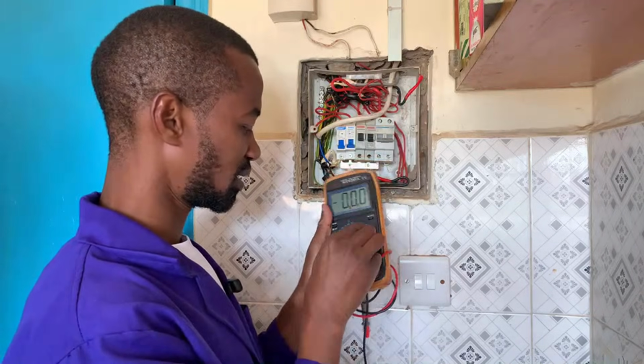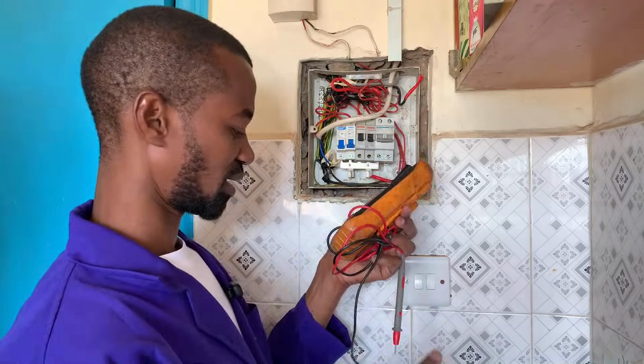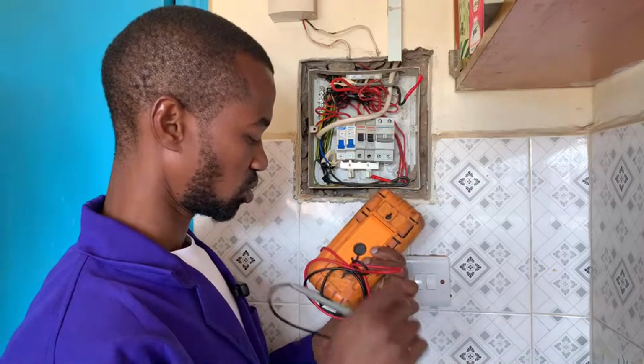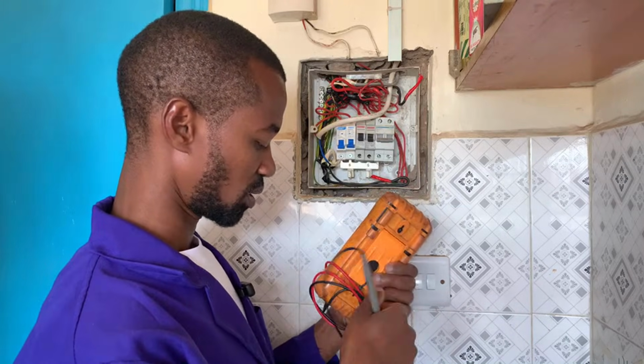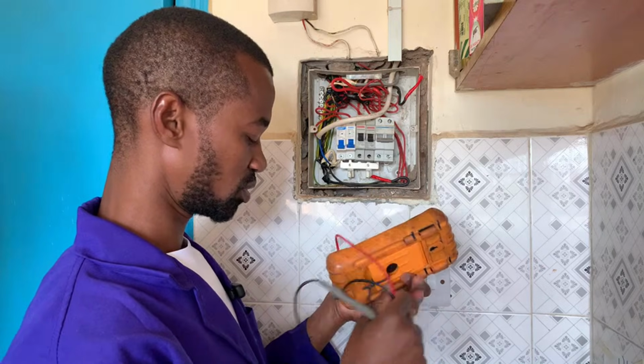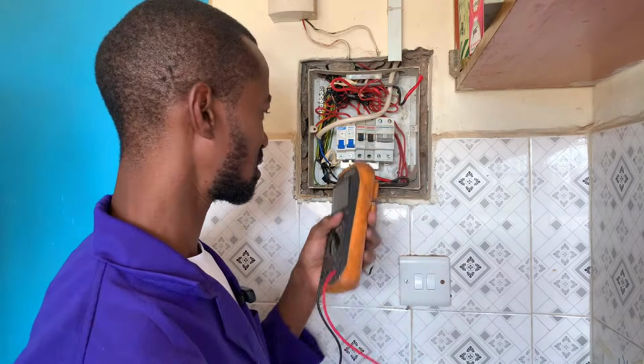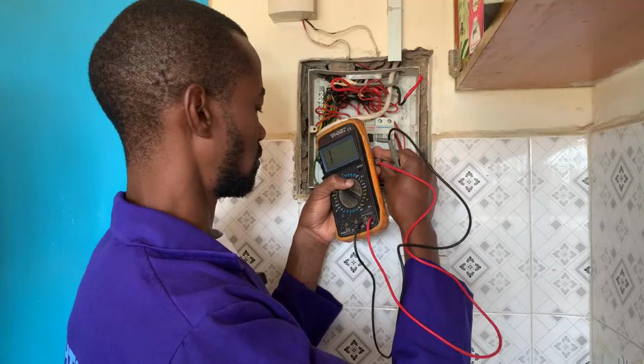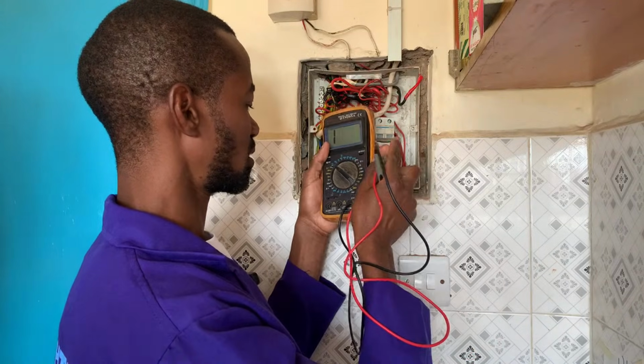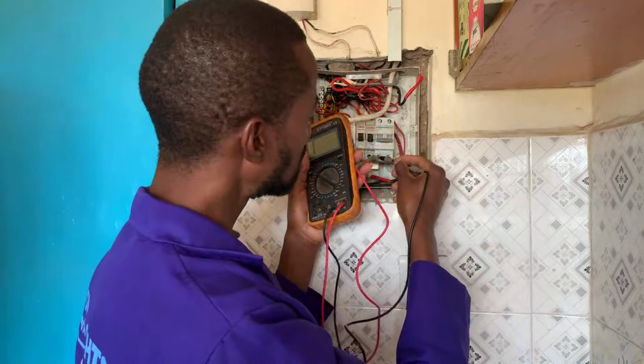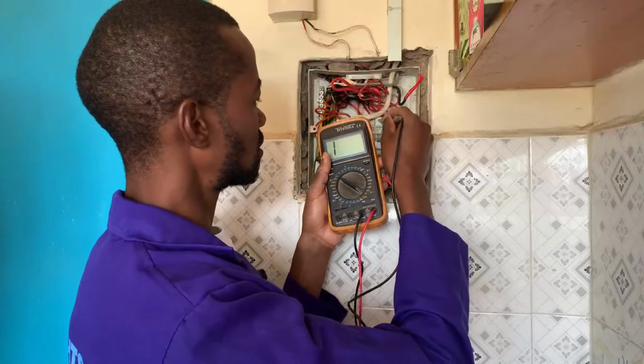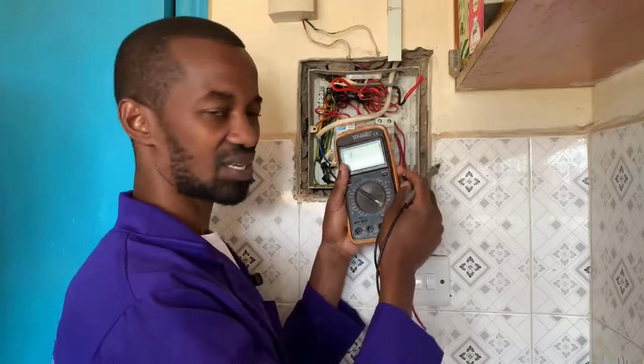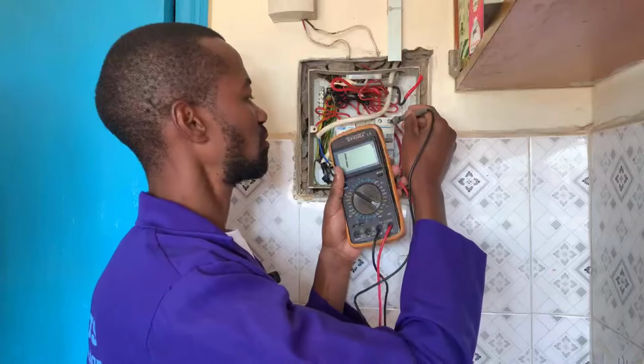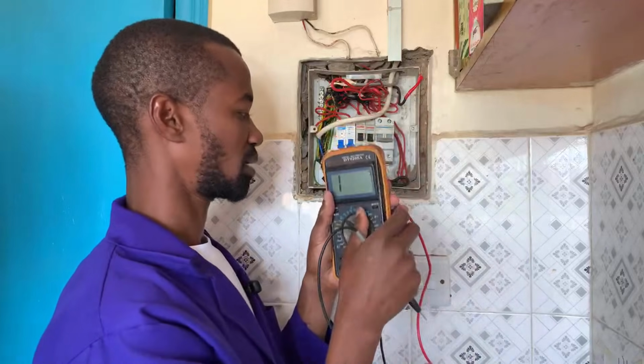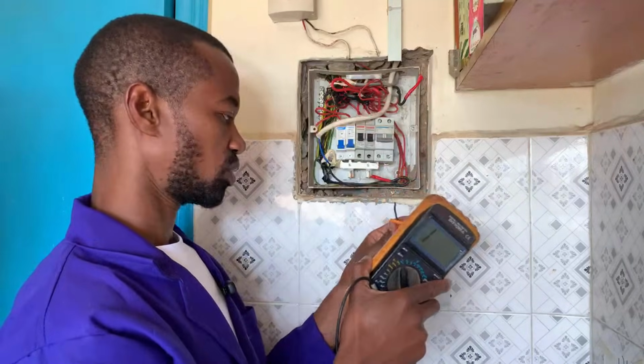One of the important tests that you need to carry out right there is the continuity - the continuity between the neutral input and the output when it is on, and when it is off. At the off position, we want to test for continuity, which should be open, meaning that current cannot flow even if we connect it back. All right, and also to ensure that...